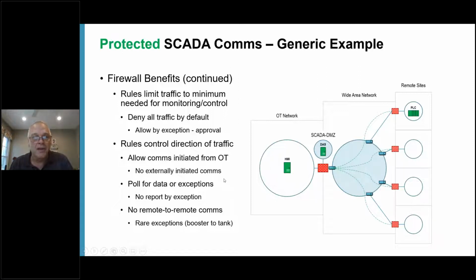So what we can do is say all traffic will be allowed out of the firewall so that it can request information from the PLC, and then the PLC can respond. Some protocols like DNP3 are very efficient, and when something changes, it communicates to the central site. That's great, but it's not great for cybersecurity.